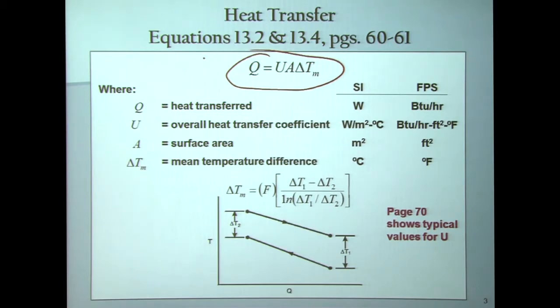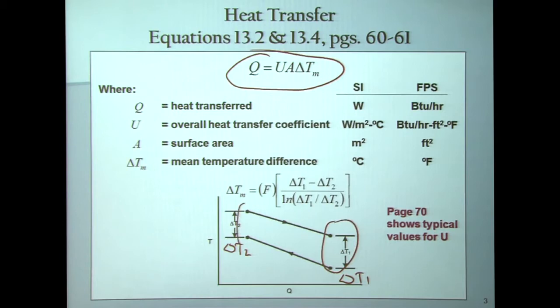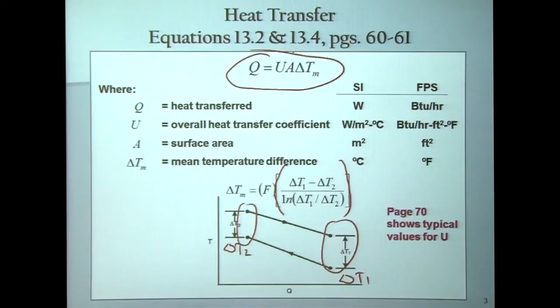The driving force is the temperature difference at the hot end of the exchanger — delta T2 — and the temperature difference at the cold end of the exchanger — delta T1. This is called the cold approach, and this is called the hot end approach. We use this log mean temperature difference in order to get an average temperature difference between the two streams. This is the guiding principle — this rate equation — to determine the area of a heat exchanger.